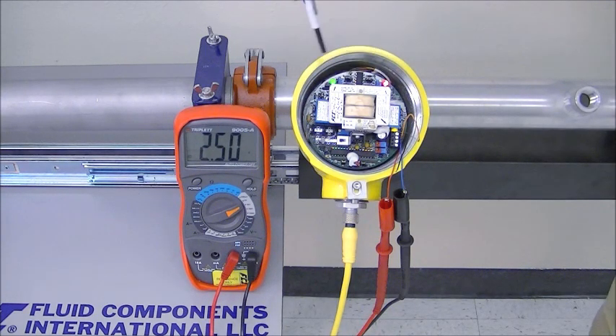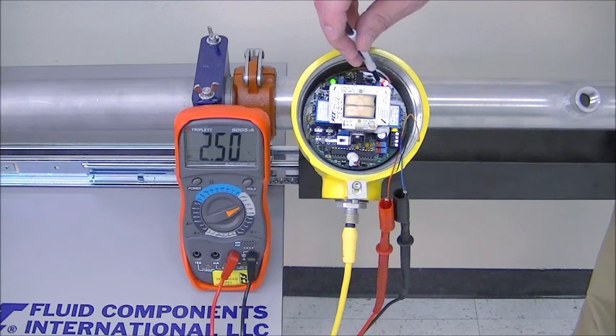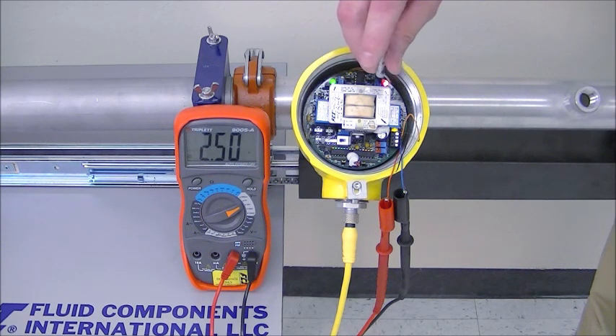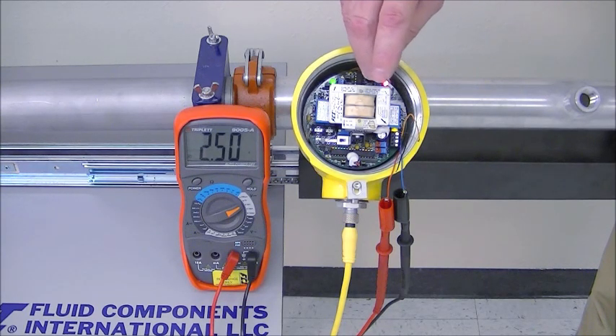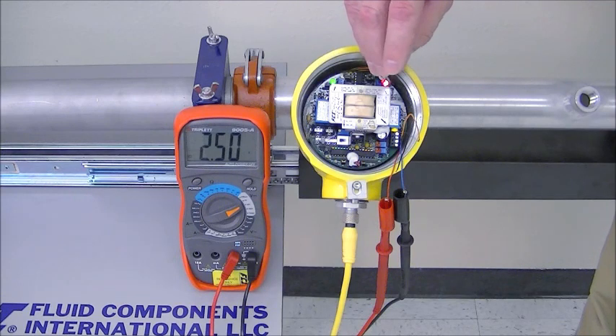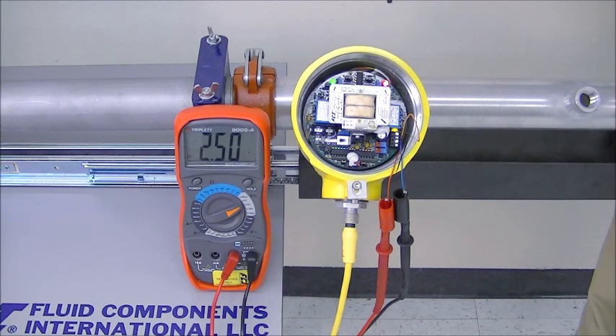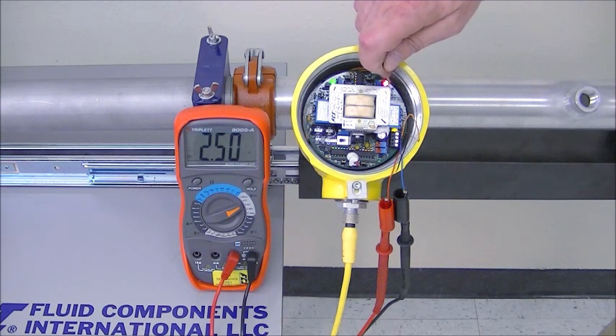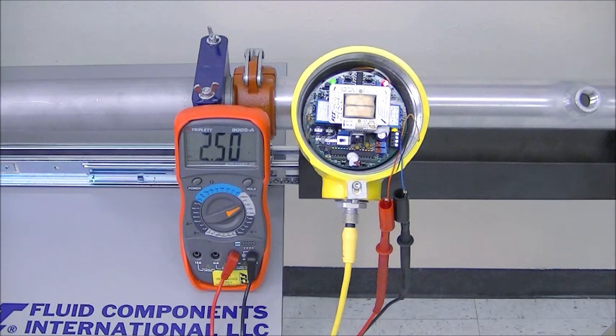Now I'm simulating a flow condition that's right between flow and no flow. And so I can set my alarm. I'll come up here to potentiometer number R26 for alarm number one, right next to the red LED. And if the LED is on, I'm going to go counterclockwise until it goes off. And then I'm just going to go back again until it's on. Now, I'm setting an alarm to detect a loss of flow condition. So I want to have the LED on to indicate a loss of flow. Think of these alarm LEDs like stop lights. When they're on, it indicates a loss of flow. It's like stopping. The flow is stopped. So I want the alarm condition to have the LED on.